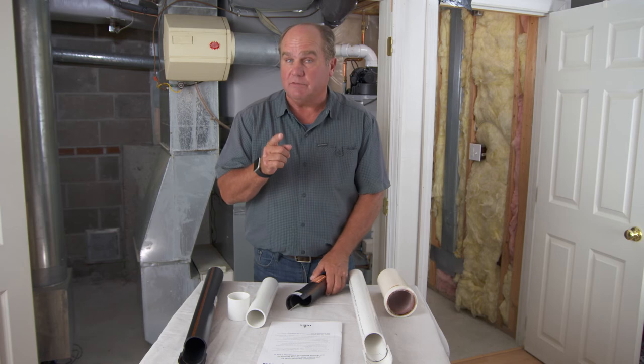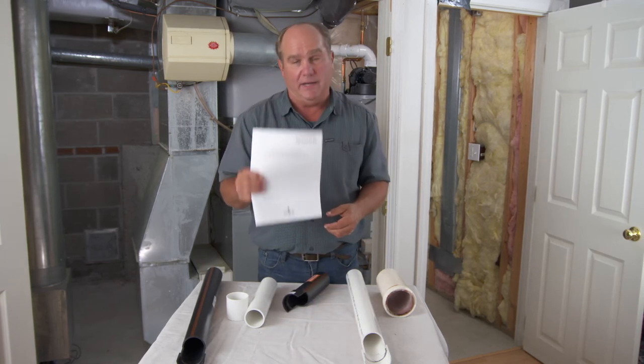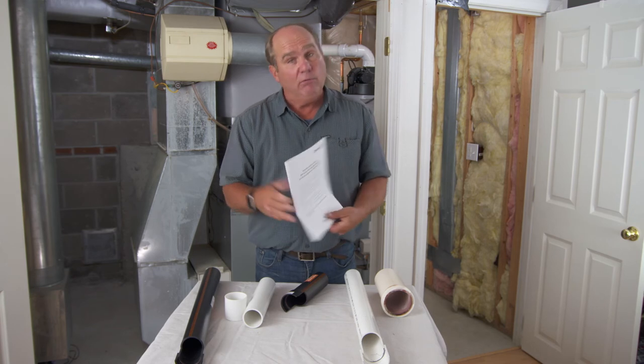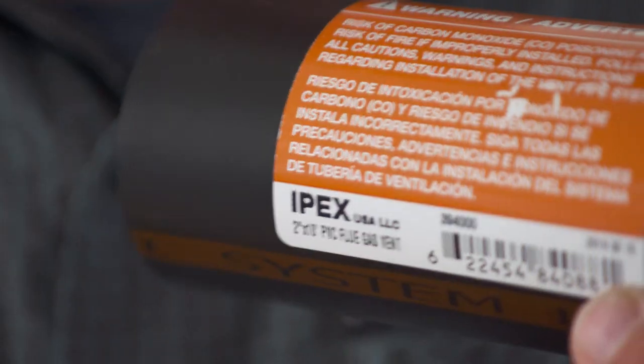The other thing that the standard specifies is that there needs to be a comprehensive installation manual provided by the manufacturer. And how would you know whether the pipe is rated for vent piping?